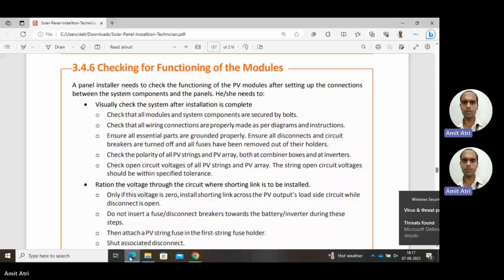Then after that, he should check all wiring connections are properly made as per the diagrams and instructions. So there should not be any type of mistake or error in the wiring. He should ensure that. So yeah, next he should ensure all essential parts are grounded properly. Okay, so now including the disconnects and circuit breakers. So all types of connecting or disconnecting devices, circuit breakers, they are turned off. All fuses have been removed out of their holders. But this is for safety reasons.